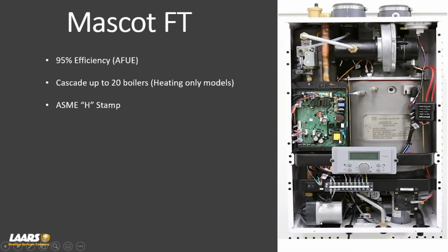We removed the cover here. This is a 140 combi. We have a built-in gas leak detector right on the circuit board. So here's our circuit board, gas leak detector. So if we ever had a gas leak in the cabinet, that would fault, give you an error code right on the display that could be reset. Obviously, you'd have to check for a gas leak prior to resetting.